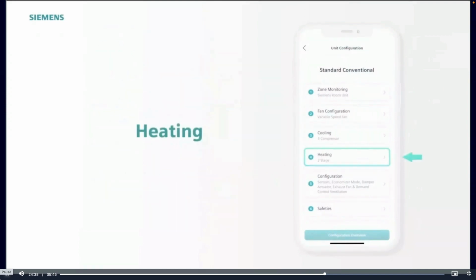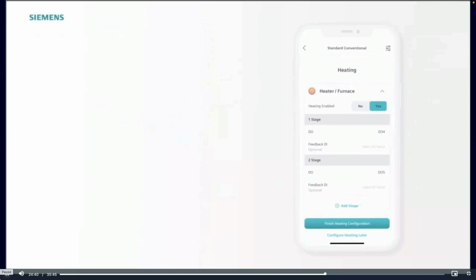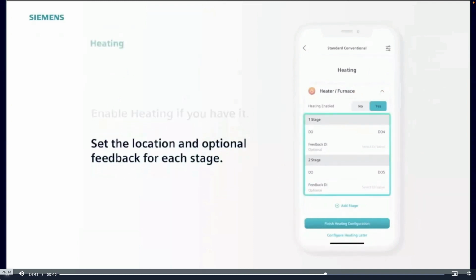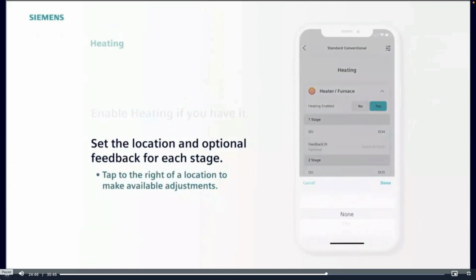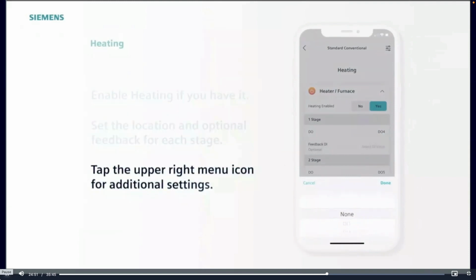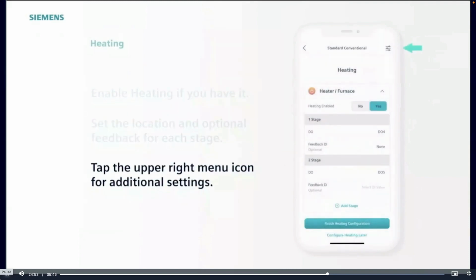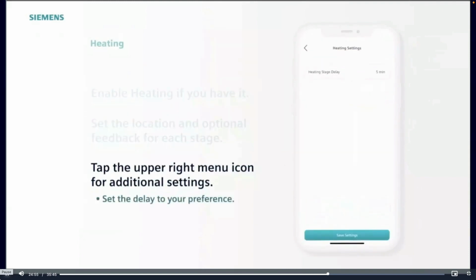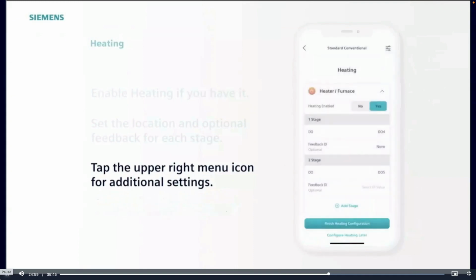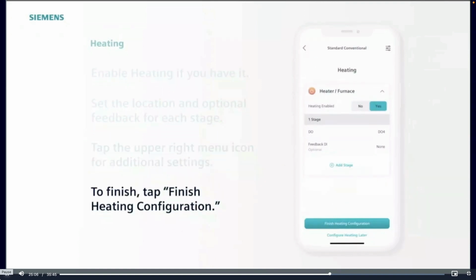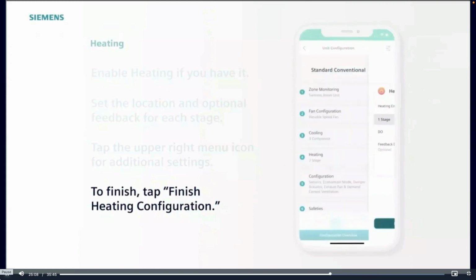Next step, select heating. There are 2 stages set at default DO locations. Feedback can be set optionally by tapping the area to the right and selecting the location. We won't select a feedback for this example. Once again, tap the menu icon at the top right to set the delay. We'll leave it at default for this example, and tap Save Settings. You can delete unneeded heating stages the same way you delete unneeded cooling stages, by swiping left. And finish by tapping Finish Heating Configuration.